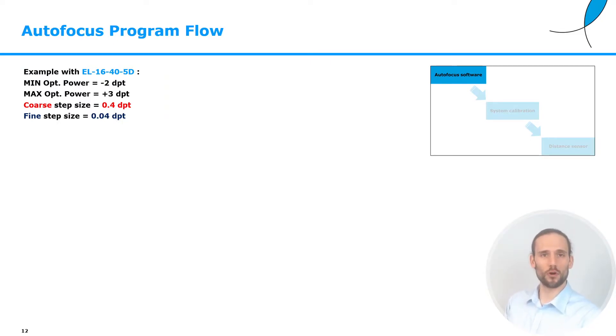Let's now look at the autofocus program flow. We will do this with the help of a block diagram. Let's suppose that we have our system that is ready to acquire images. What we will do is place the object at an arbitrary distance, then we will set the optical power of the lens to its minimum value. For example, for the EL-1640, the minimum value could be minus two diopters. Then we will define a coarse step size. For example, it could be something like 0.4 diopters.